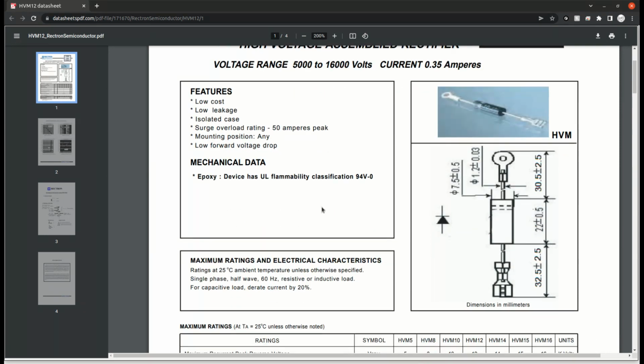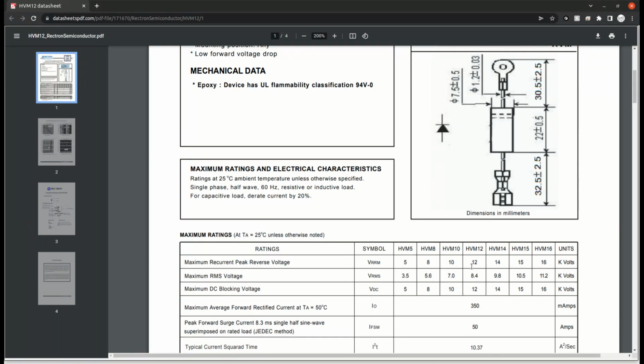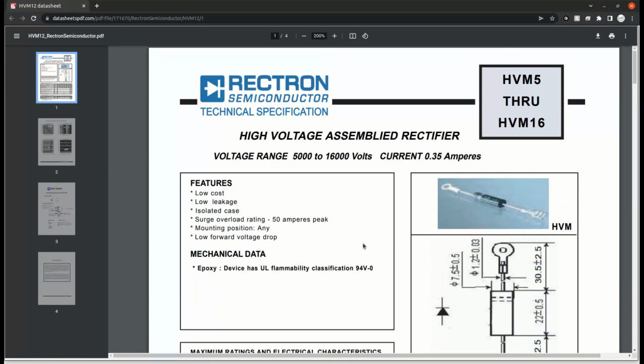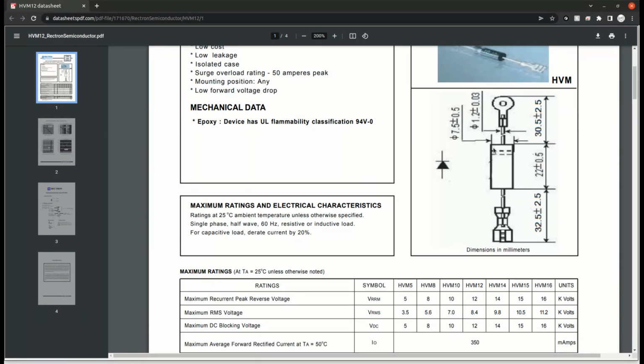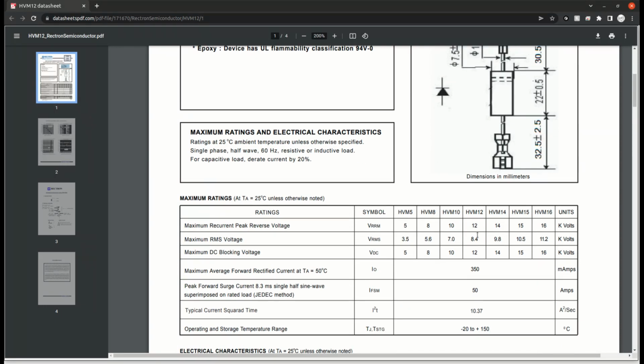Right, so we've got an HVM12. Maximum recurrent peak reverse voltage, 12 kilovolts - not enough. Maximum RMS voltage, 8.4 kilovolts - not enough. Maximum DC blocking voltage, 12 kilovolts - not enough. What we're going to end up doing - if you see these assembled rectifiers, they're literally just a stack of diodes in there - is stack two lots together. That gives us 24 kilovolts, 16.8 RMS, which is more than the 14 or 16 we're probably going to see, and that's going to be fine.